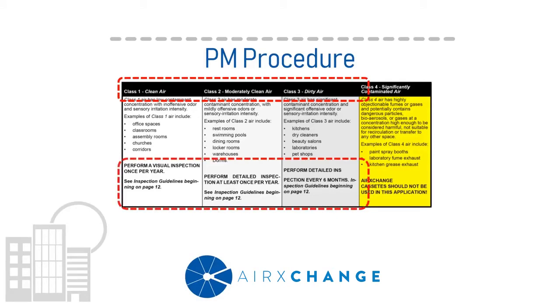Most building types are going to fall into Class 1 and Class 2 air. For those classes of air, we recommend an annual inspection on these devices. For Class 3 air, we recommend an inspection every 6 months. As you get more familiar with the device, you can further modify the schedule to best suit your building type. I would also suggest performing this inspection during the shoulder seasons where the conditioning load from the ventilation isn't at its peak or too severe.